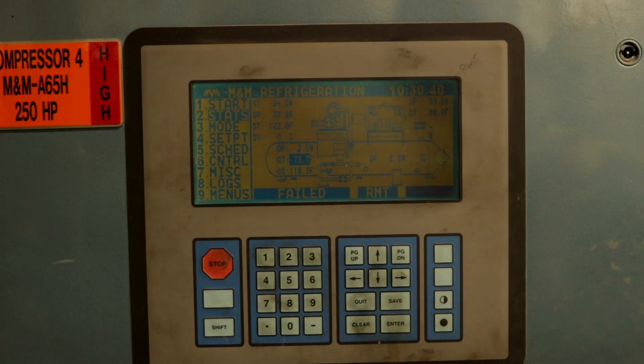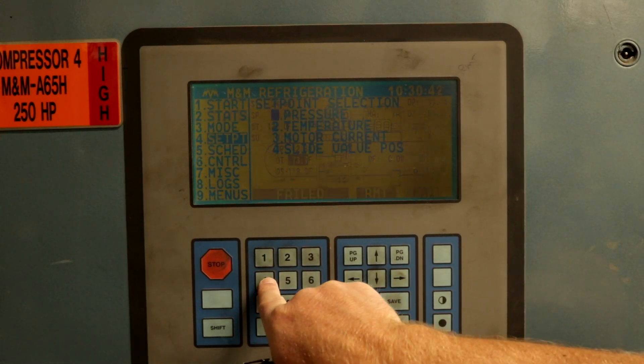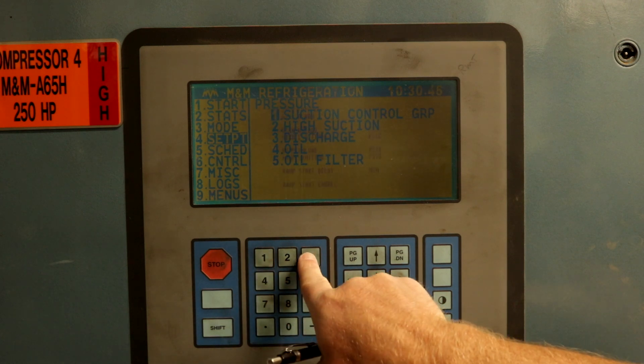VFDs, however, are expensive and generally are not justified if a compressor will operate fully loaded most of the time. For this reason, systems with multiple compressors may only equip the trim machine with a VFD.